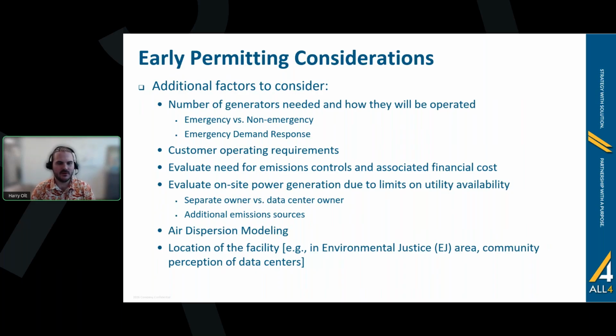Federal rules currently prohibit non-emergency operation for financial arrangement by emergency engines unless five specific criteria are met. This means engines from 2011 or later, currently Tier 4 certified, would need to operate outside those five criteria. Aaron Sabot from EPA's Office of Air announced at a conference at the end of March that they plan to revise the regulations this summer to allow operation of Tier 4 compliant engines for demand response.